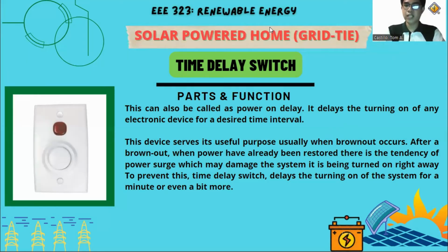To prevent this, the time delay switch delays the turning on of the system for a minute or even a bit more. So yung time delay switch na tinatawag ding power on delay will delay the electrical connections for like a minute until the power stabilizes. By doing so, your electronic devices are protected from the expected post-brownout voltage surge, which in turn ensures the continuous safety and performance of your electronic devices or appliances.